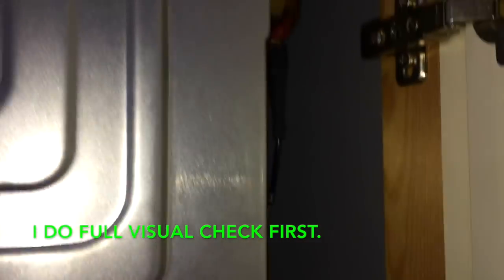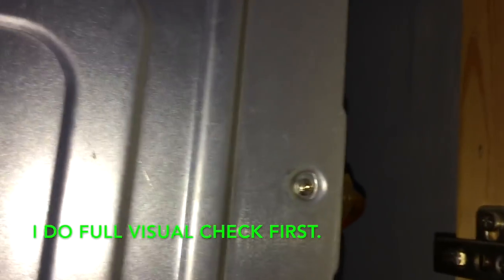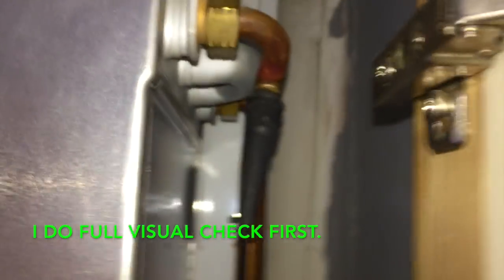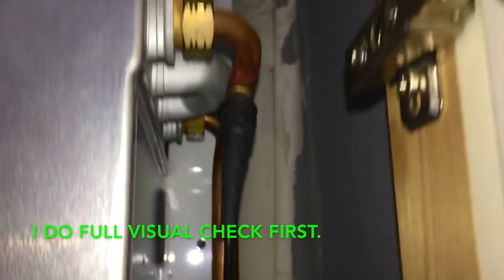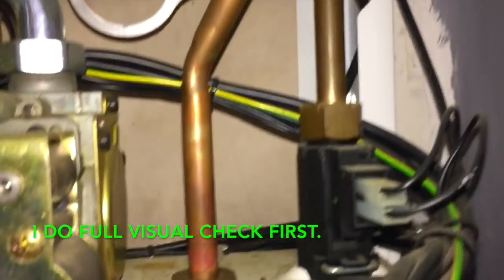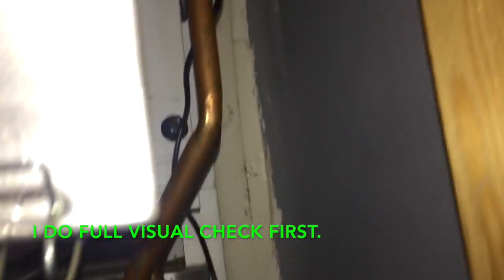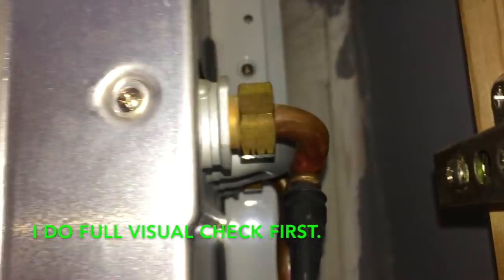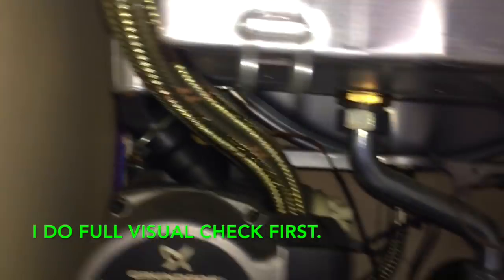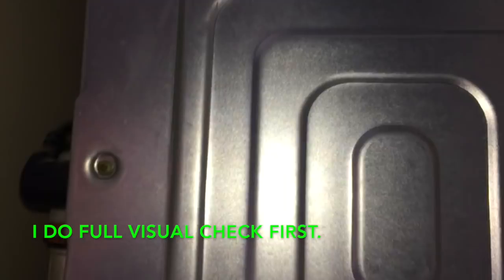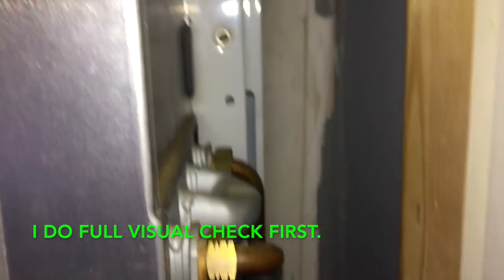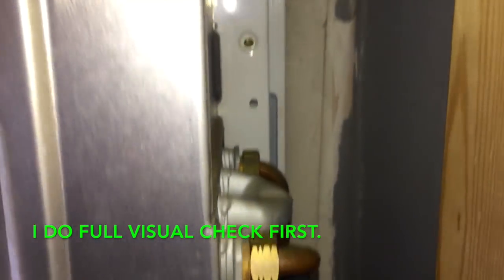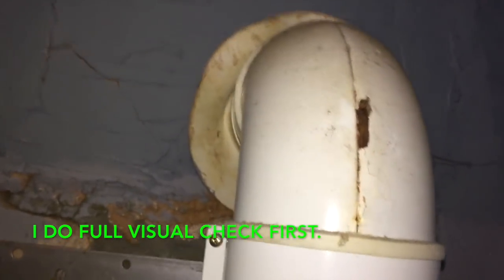So this is what's known as a bithermal heat exchanger. I'm just going to flip this round. Because this heat exchanger has 4 pipes going to it, there's the mains in, there's the hot out. Simply runs up there, goes through that main heat exchanger, as well as the flow and return, which are these pipes here, that one there and that one at the back. So because all 4 pipes run through that heat exchanger, called a bithermal heat exchanger, this is quite old technology now. Modern boilers aren't made like this. So let's do the fluid checks while we're here.